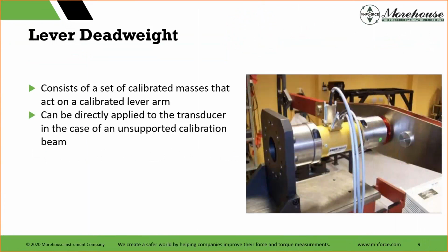So talking about primary standards, this is where we're going to take some time and just explain some of them, explain some of the errors. You know, this is how typically if you're just doing wrenches, that torsion cell has to be calibrated somewhere. Is it calibrated with arms, weights? Is it calibrated by transfer? All of this stuff. The most common way to do this is the lever deadweight systems, and it consists of a set of calibrated masses that act on a calibrated lever arm, and it can be directly applied to the transducer in the case of an unsupported calibration beam. Now, a lot of people unsupport the arm, and we'll talk about some of the pitfalls to that and what you may do to quantify the errors in your system, because it is a lot more than force times length here on the system.